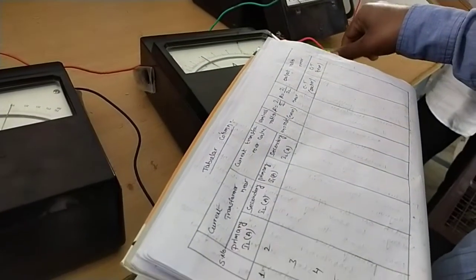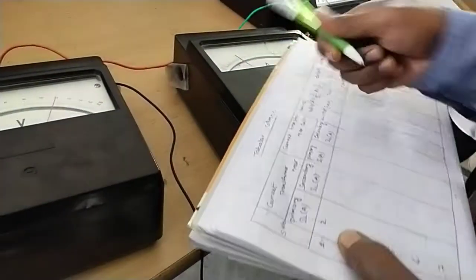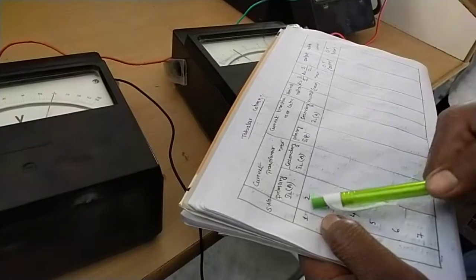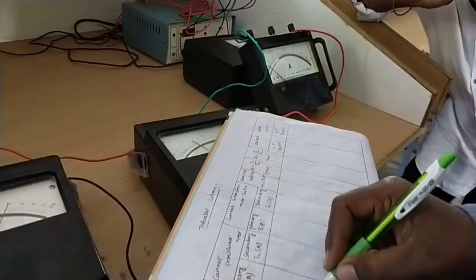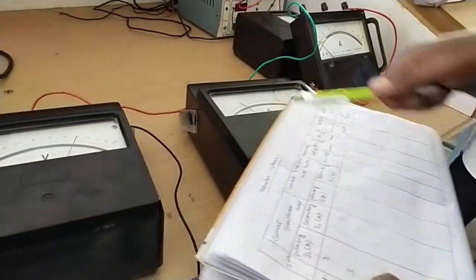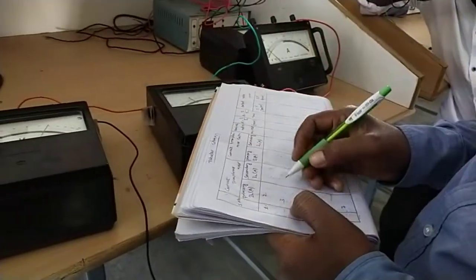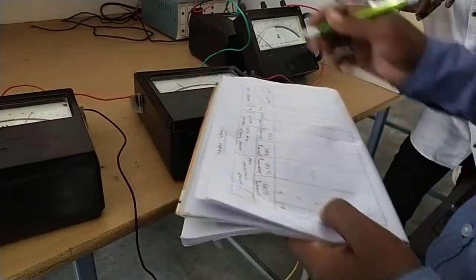For a primary current of 4 amps, first we set 2 amps. For 2 amps primary current, the secondary current is 0.1 amps. Now increasing to 4 amps primary, the secondary shows 0.2 amps. Now we increase the load further and take primary and secondary current readings again. The primary is now showing nearly 6 amps.